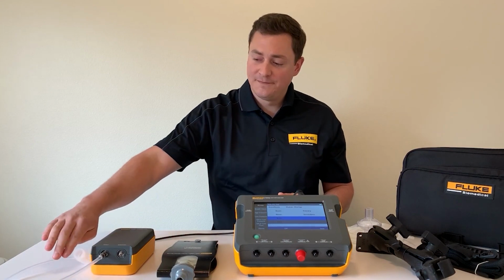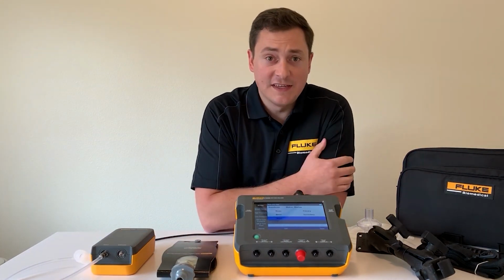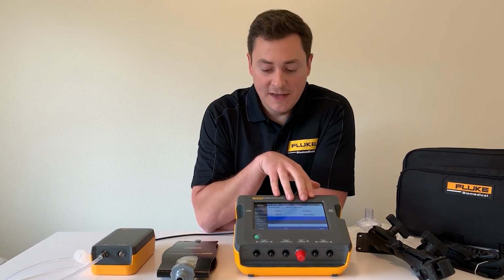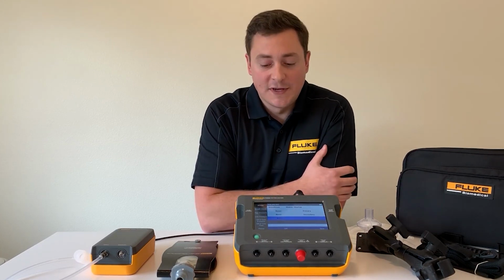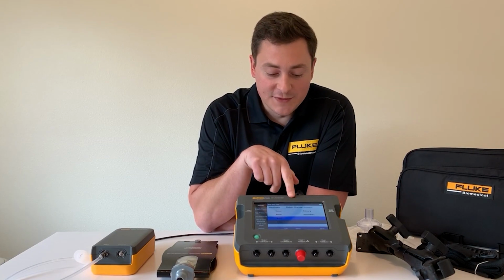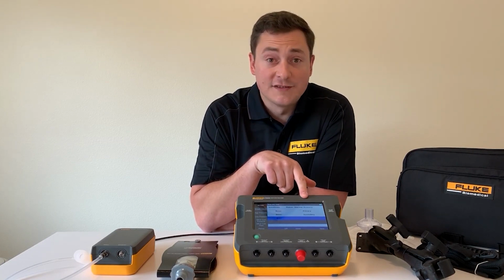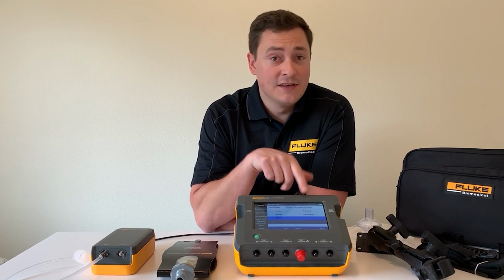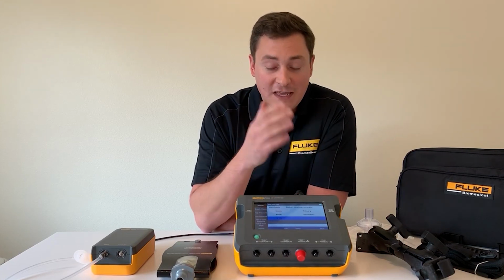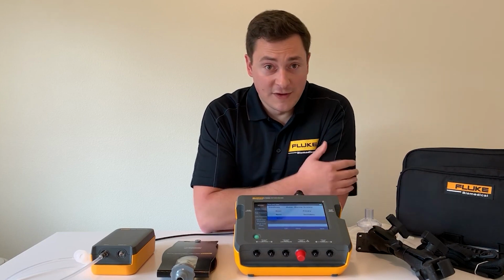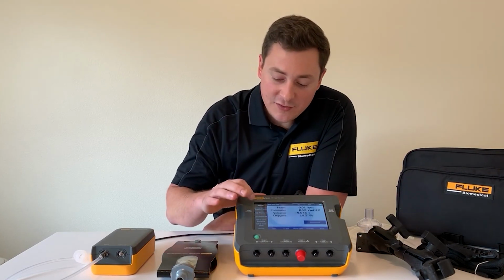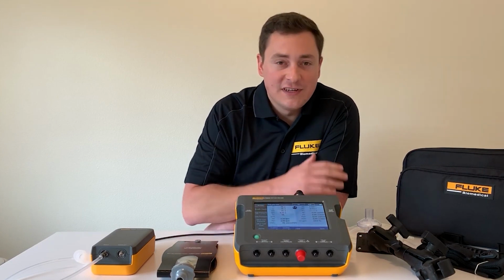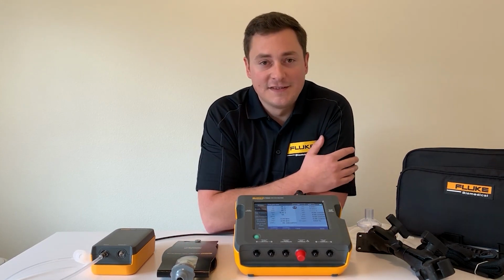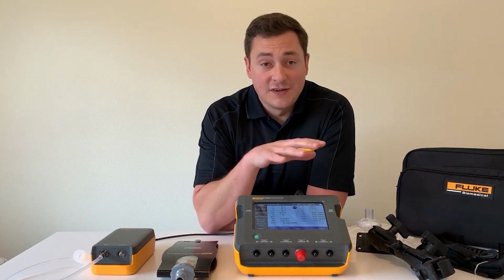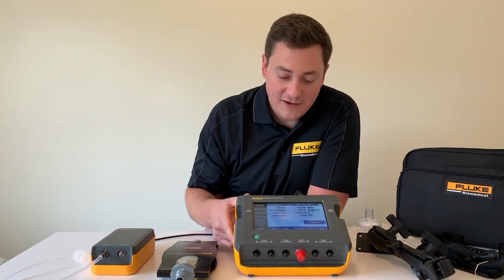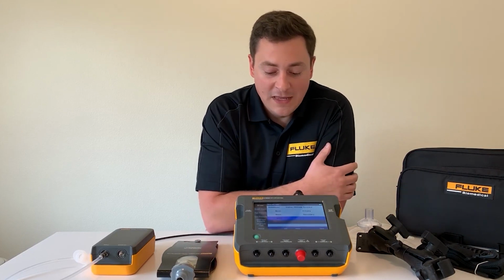This does have a warm-up time. The VT900A is basically instantaneously warmed up along with the VT650, but the vapor does have a warm-up time. So you're going to see it go through multiple statuses until it comes up to warm-up accuracy. If this meets your test procedure accuracy, you're free to go testing now. If you need to wait for full accuracy, don't worry about that warm-up time. It doesn't have to be a big deal because you can go back to the airway screen or breath view screen and do all of your ventilator testing while that warms up, because it's going to keep that going. So no big deal there. You don't really have to worry about that warm-up time.